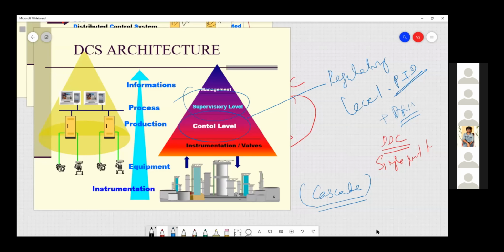This has to be converted, first of all, by means of a transducer, which converts your process variable into an electrical quantity. Then it will go to a transmitter, which converts it into 4 to 20 milliamps, so you can transmit the variable from a process station to a control station. Most transmitters always use 4 to 20 milliamps.